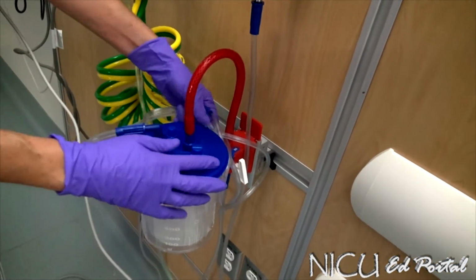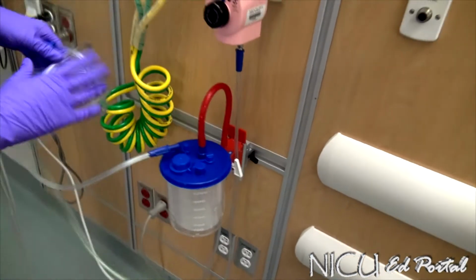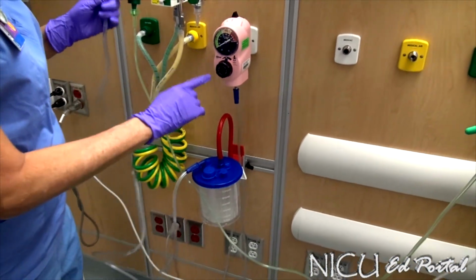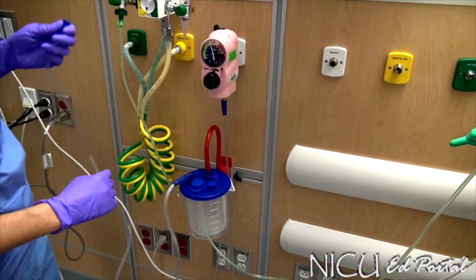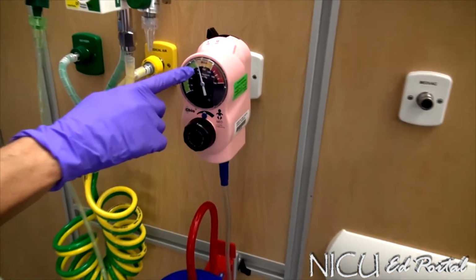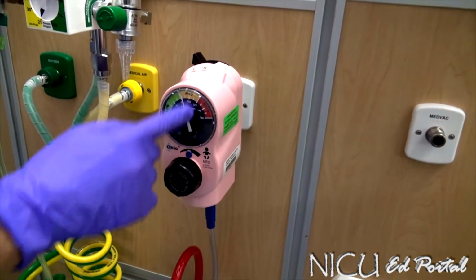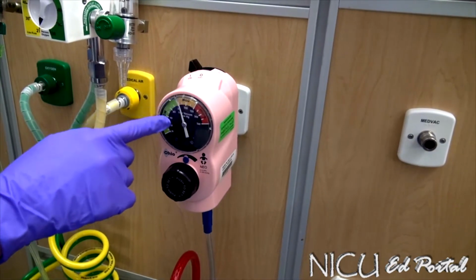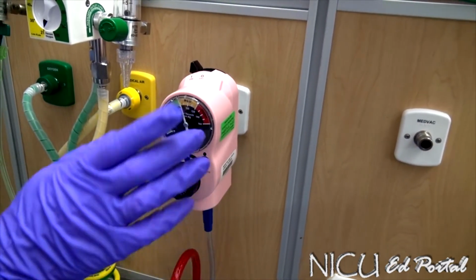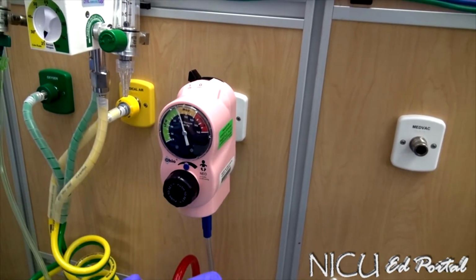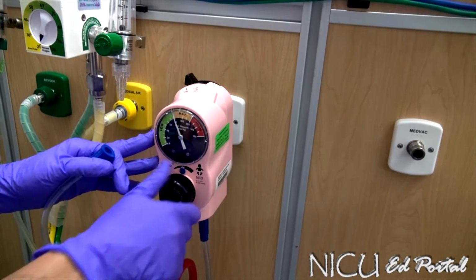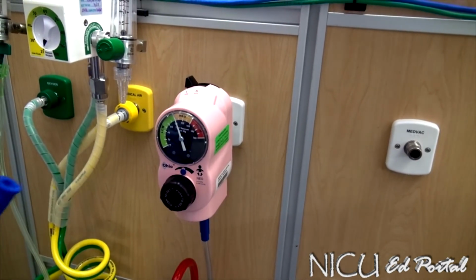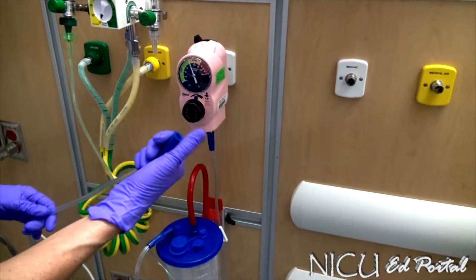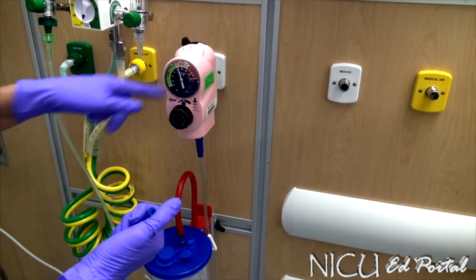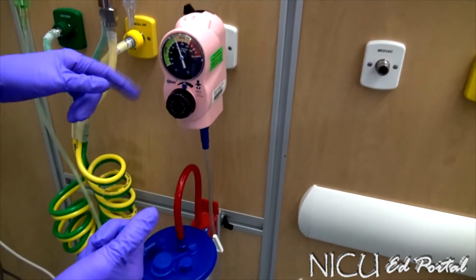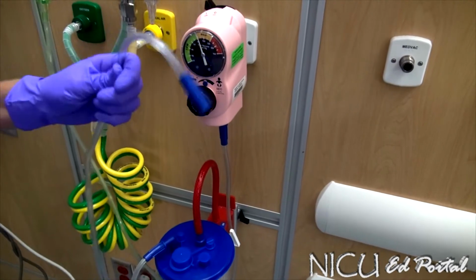So I've turned on phase 1 of the suction. The second thing that I need to do is turn on my manometer as well. Once I turn this on, what we should be seeing is that our suction is defaulting to somewhere between 80 and 100 millimeters of mercury. So if you look at the manometer, you're looking for between 80 and 100. If it's not set up to that, which sometimes it is not, you need to adjust it. So you make your adjustments here. I've made my adjustment. Let's check to see that the suction is actually working. If I put suction on the very end, yes, there we go. And we have established suction between 80 and 100. So your suction is set to go.